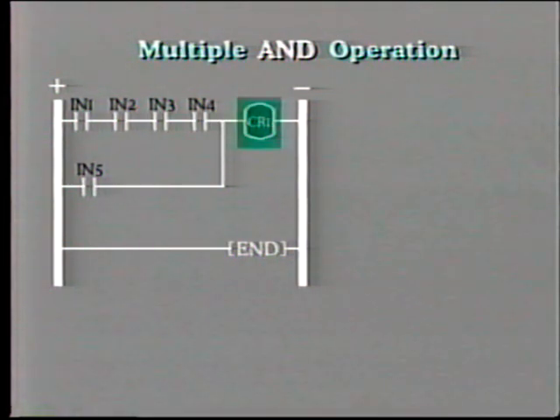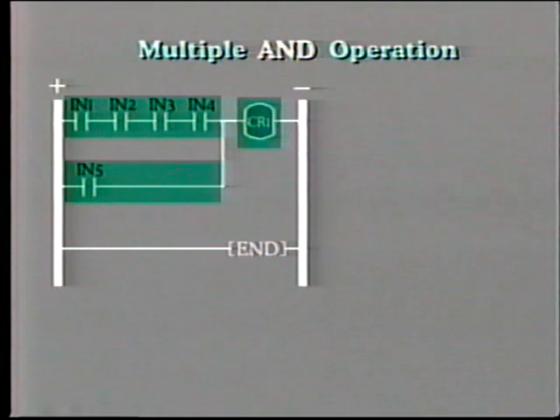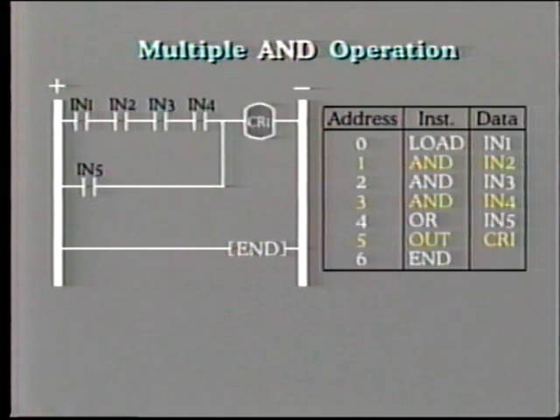The output is shown as a control relay, and this may be energized by either of the two branch circuits. Input contacts IN1, IN2, IN3, and IN4 must all be closed to energize the control relay. Or, input contact IN5 must be closed. Each of the individual input and output contacts must be given an address. In this example, they are simply numbered 0 to 4.